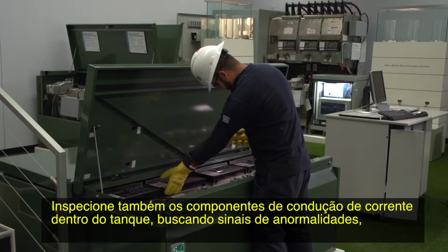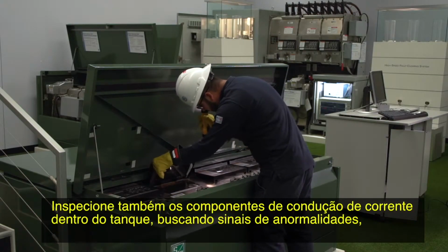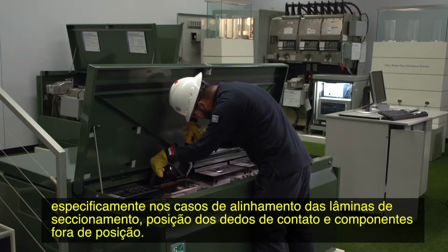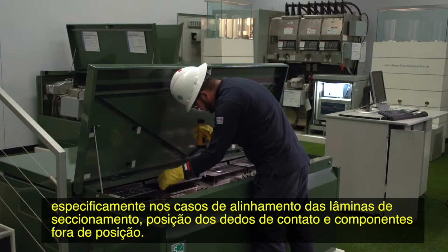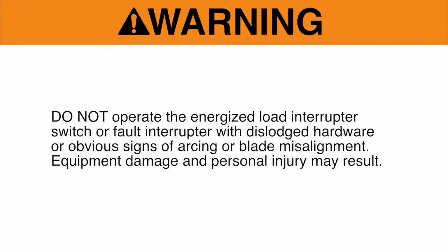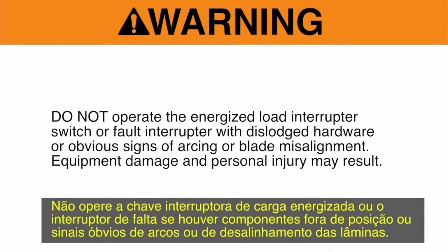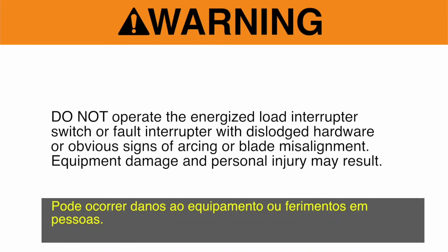Also, inspect the current carrying components inside the tank for any signs of abnormalities, but specifically for disconnect blade alignment, contact finger position, and dislodged hardware. Do not operate the energized load interrupter switch or fault interrupter with dislodged hardware or obvious signs of arcing or blade misalignment. Equipment damage and personal injury may result.